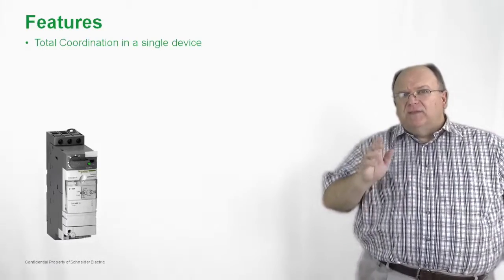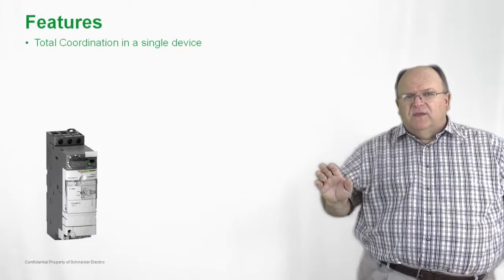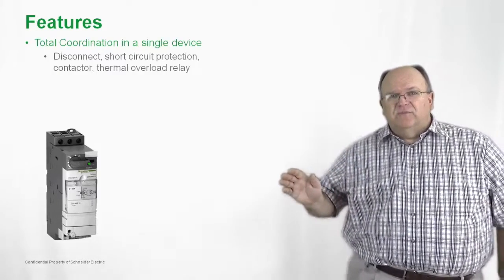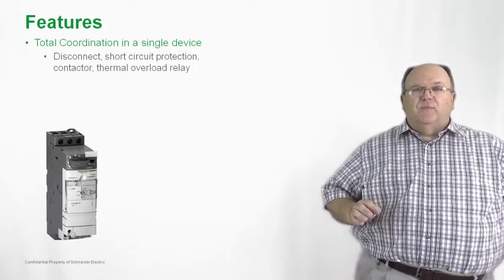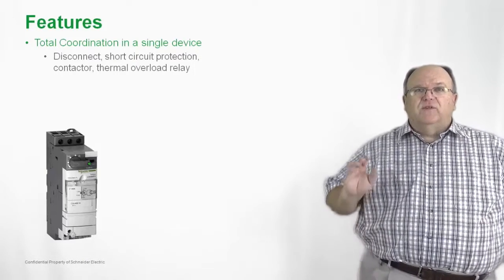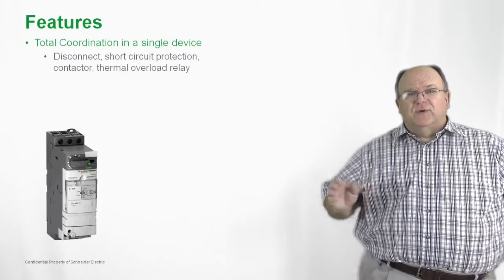For the OEM and the installer, this product is a single device. You just have one product to install, and it includes the disconnecting means, short circuit protection, contactor, and thermal overload relay. So when you go to install a TeSys U, when it comes to the power connections, it's simply three wires in and three wires out.